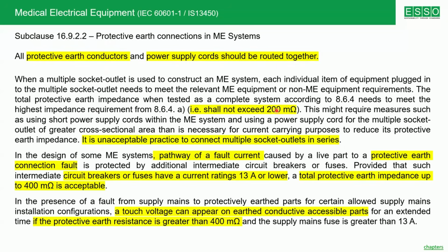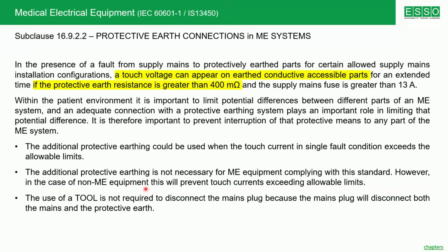So then the requirement of earthing, you can see here 200 milliohm, 400 milliohm. You can find this requirement in multiple places of the same standard. A touch voltage can appear on earthed conductive accessible parts for an extended time if the protective earth resistance is greater than 400 milliohm. In a location where you have biomedical equipment, sometimes the resistance required is less than 400 milliohm for equipment which consumes power or has a fuse of up to 13 amperes. If the machine requires higher current, then of course the resistance decreases.